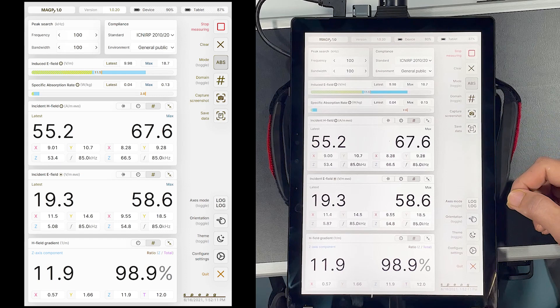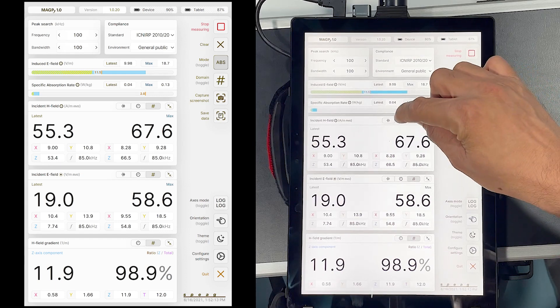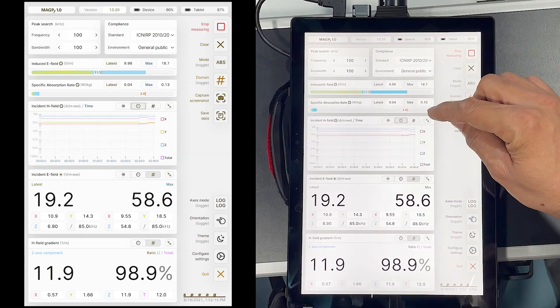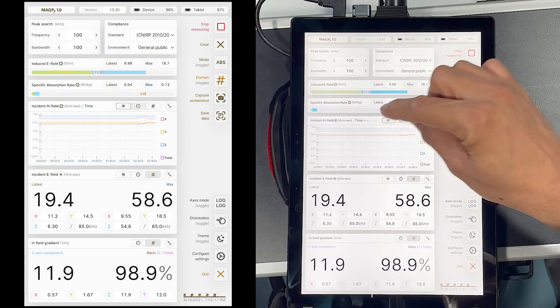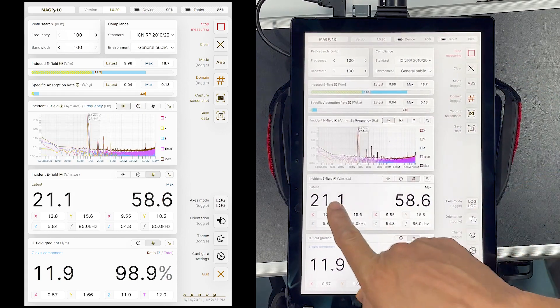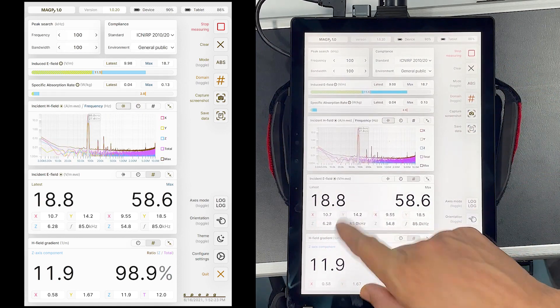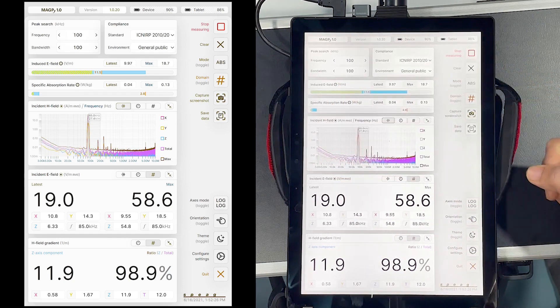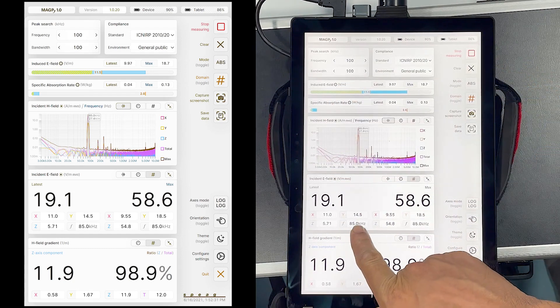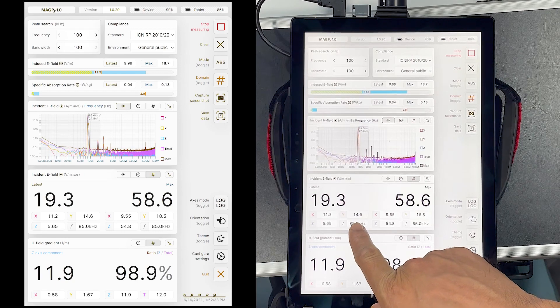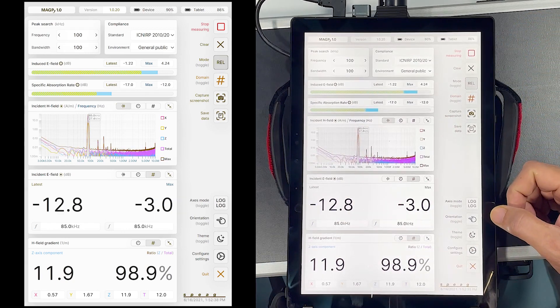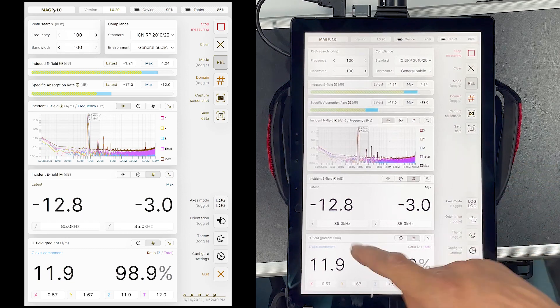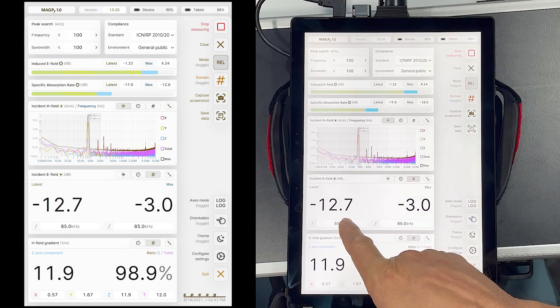The field can also be visualized in the time domain. The incident E field value is shown in this window here. These are quite low as this is a magnetic field source. If I switch to relative mode, we are indeed 12 dB below the limit for incident E field values.